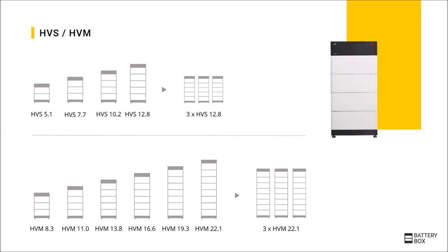At the HVS, a module has a capacity of 2.56 kilowatt hours and a voltage of around 100 volts. The modules are in direct series connection. So you can start with two modules and 200 volts, which corresponds to a capacity of 5.1 kilowatt hours. The number of modules can be flexibly chosen between two and five modules. With five modules, this corresponds to a maximum of about 500 volts and a capacity of 12.8 kilowatt hours.